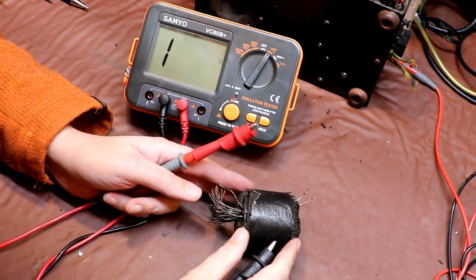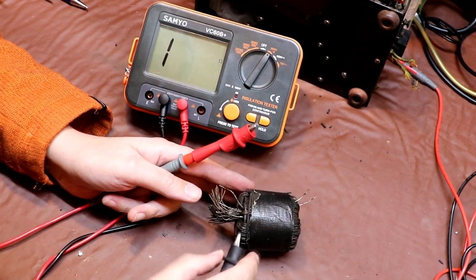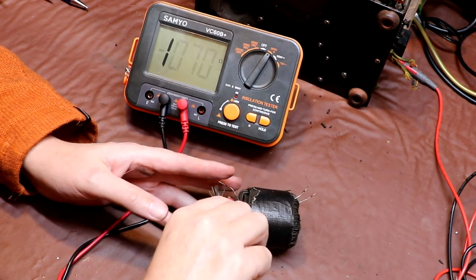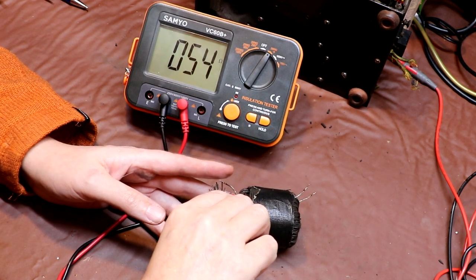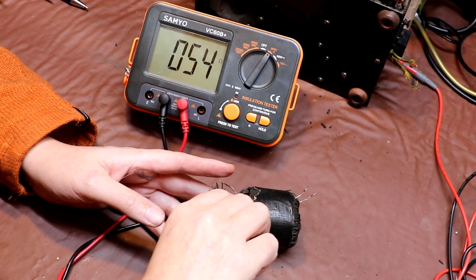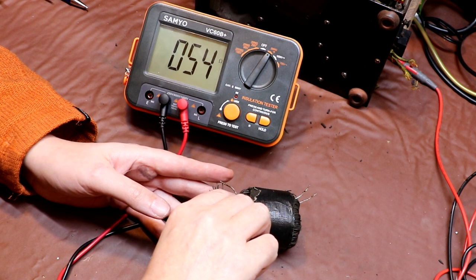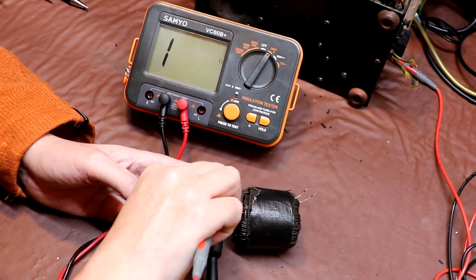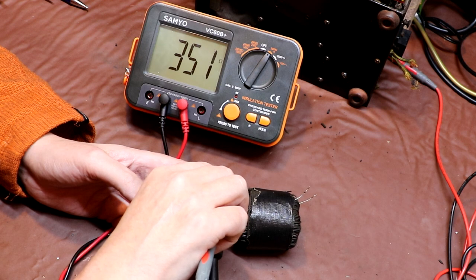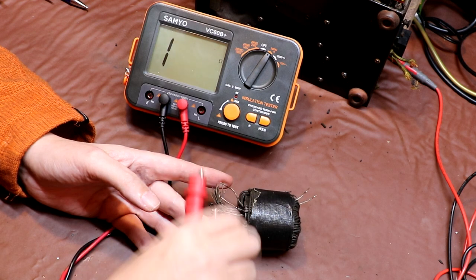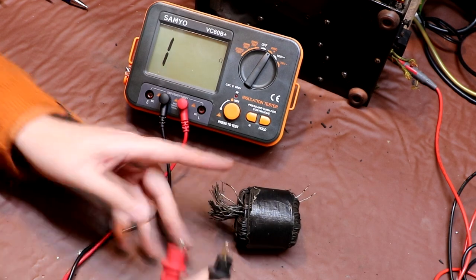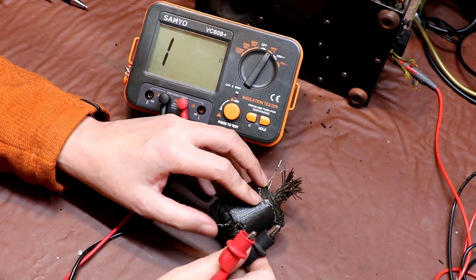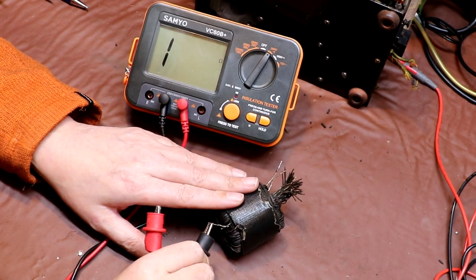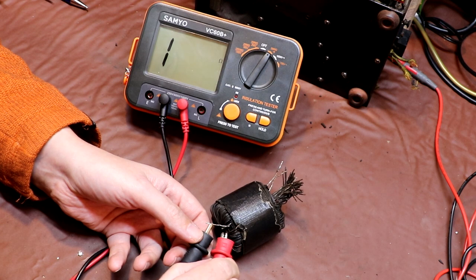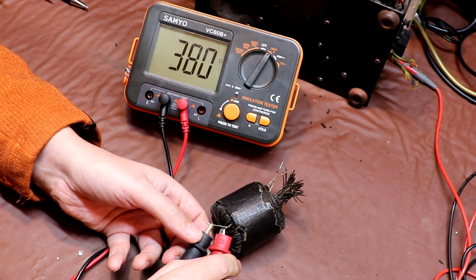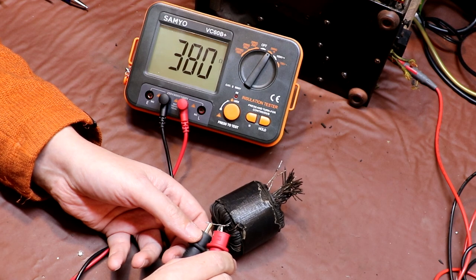So I think we'll make a start by just testing the continuity of the primary windings, so let's do that. So 54 ohms, so I suspect that that's one of the tappings we've got there. And then 350 ohms to the far end of the winding. I don't know what the value should be, but that doesn't seem too disastrous. That's probably about what I'd expect. And I would have thought that the secondary is probably not too dissimilar. Okay, so that's 380 ohms, so definitely in the ballpark.